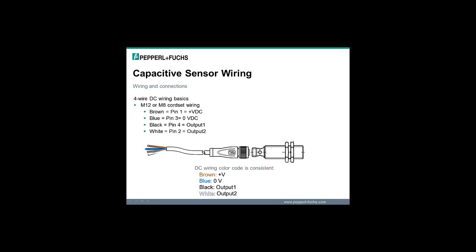When using a 4-wire DC sensor, the connection convention follows the 3-wire connection color code with the addition of the 4th white wire which connects the 2nd output signal. Here you can see that when using a 4-wire cord set, the wiring colors that you connect to use the sensor are brown, blue, black and white.